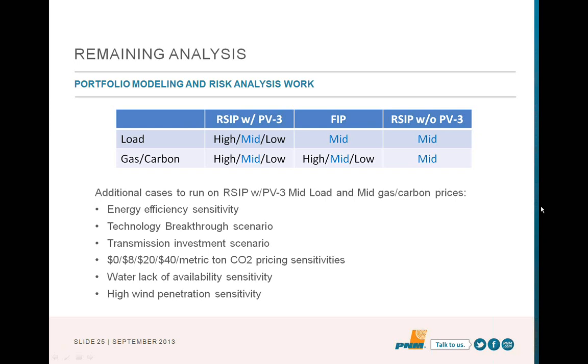And then to get to why we think the mix now works: San Juan's an around-the-clock 24/7 resource. We're able to replace some of that with an around-the-clock 24/7 resource in Palo Verde 3. Then we're also replacing some of that with a solar resource, which has a characteristic that does a good job. It's not perfect, but it does a good job of matching the increase of demand over the baseload. The solar is there through the summer hours when the load goes up. So the combination of the solar and the Palo Verde gives us a good replacement for the energy we need. And then that combination isn't perfect.